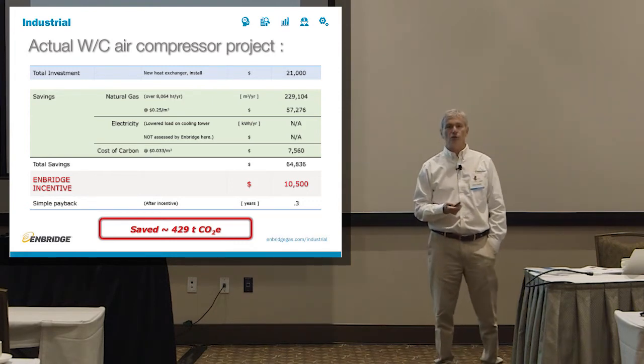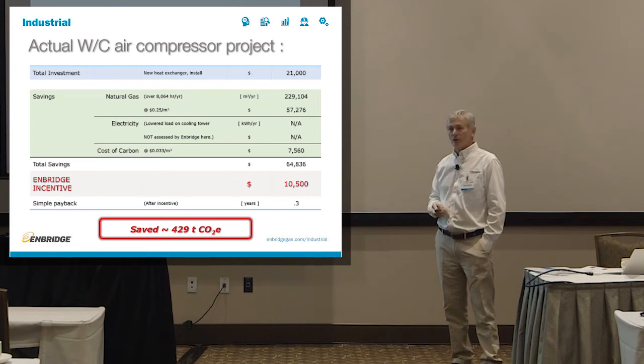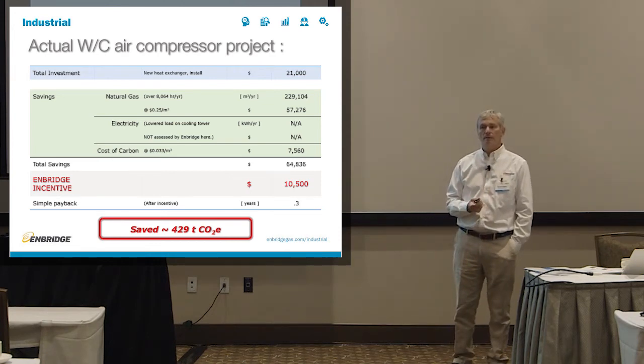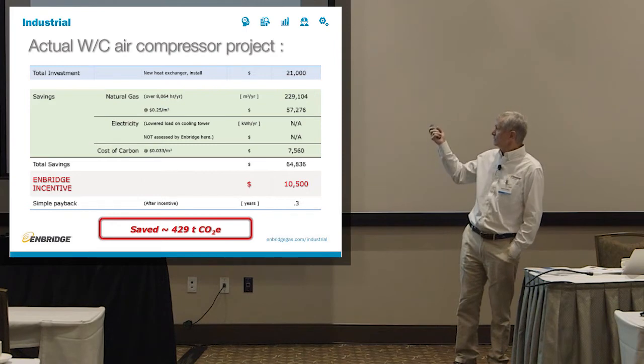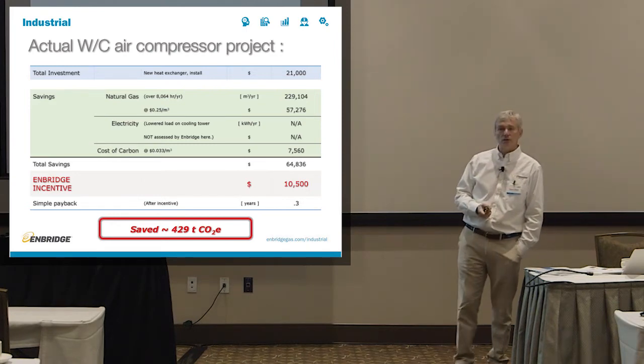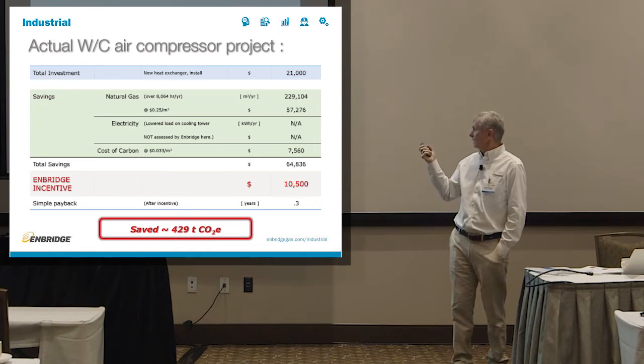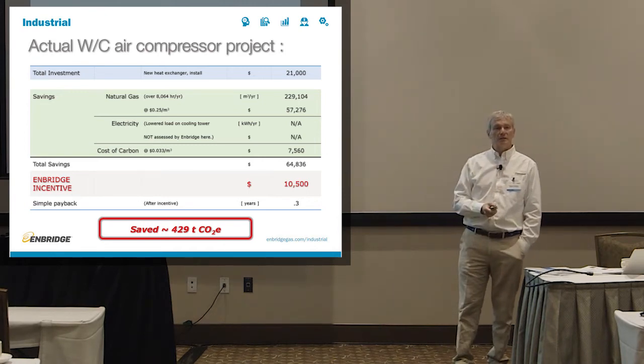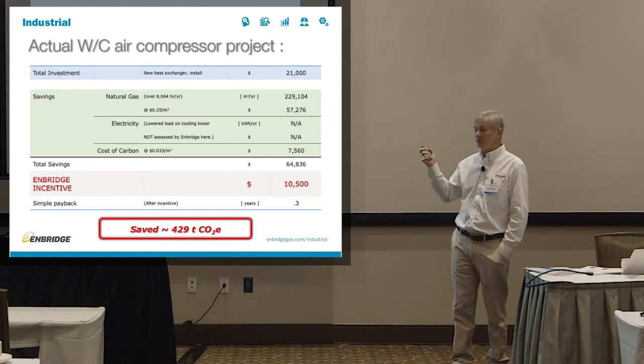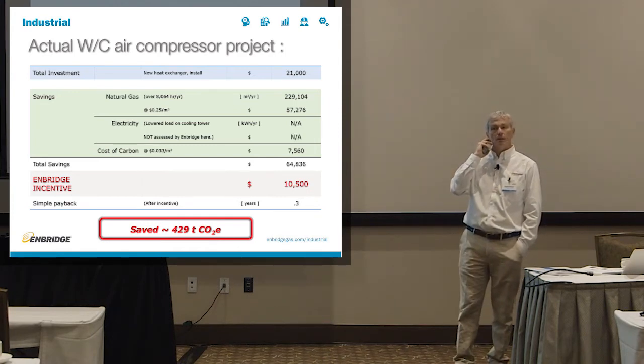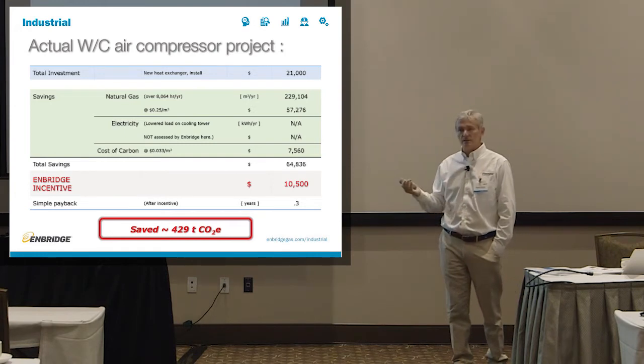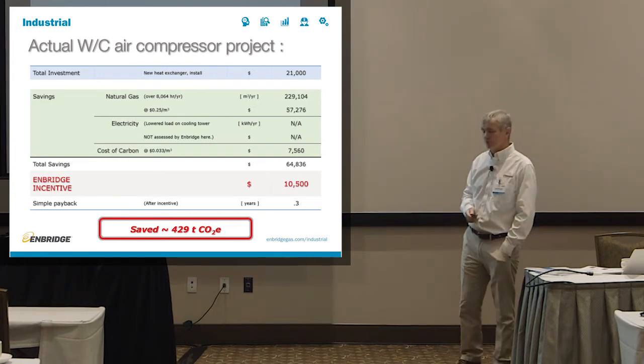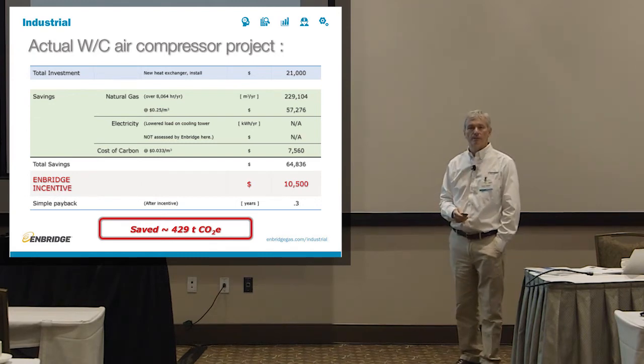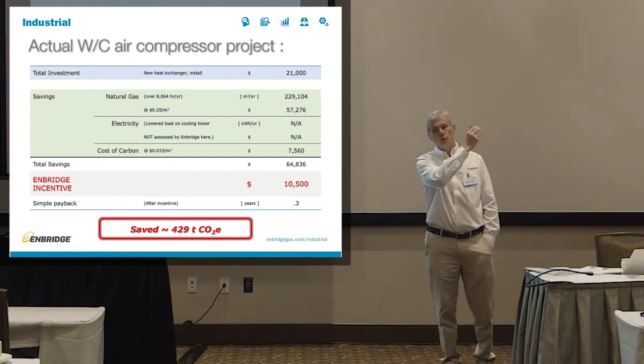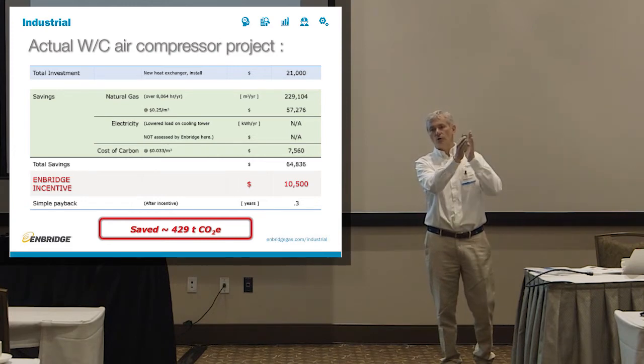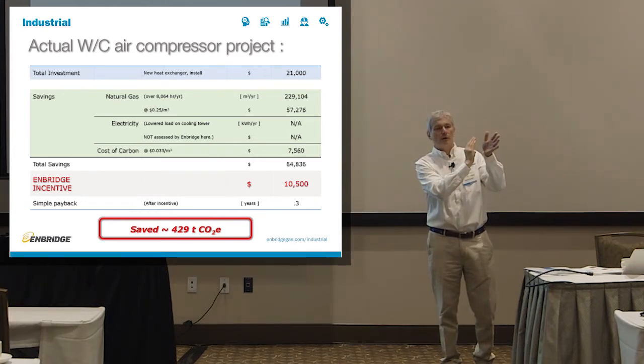$21,000 worth of heat exchanger and installation saved them 230,000 cubic meters. Those are savings of about $65,000 at today's prices. And we gave them a $10,000 incentive, so a 50% incentive. For $10,000, they are saving $64,000 a year. Payback is 0.3 years, and they're saving about 430 tons of CO2 equivalent. All it took is cutting into the two pipes that were running next to each other, one going to the cooling tower, one coming into the boiler room for the makeup water.